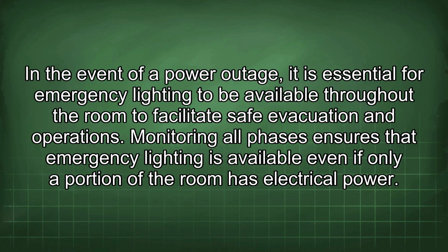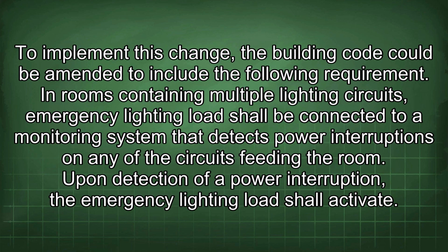In the event of a power outage, it is essential for emergency lighting to be available throughout the room to facilitate safe evacuation and operations. Monitoring all phases ensures that emergency lighting is available even if only a portion of the room has electrical power. To implement this change, the building code could be amended to include the following requirement. In rooms containing multiple lighting circuits, emergency lighting load shall be connected to a monitoring system that detects power interruptions on any of the circuits feeding the room.